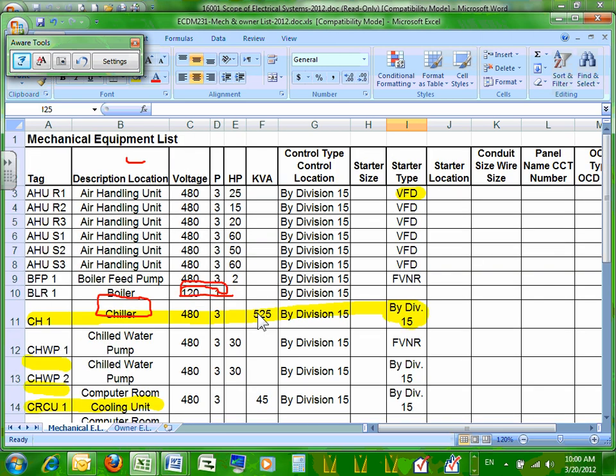Chillers are funny. We don't always believe their numbers. So we really want to see off of the data sheet what the amps or KVA actually are for that load at the chiller. And we're supposed to list the motors and take the highest, so you include that in the listing if we are trying to figure out what motors we have. I assume it has a motor. I don't know how it works out.